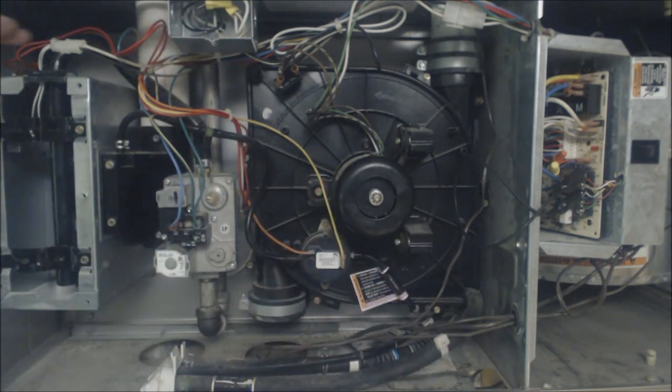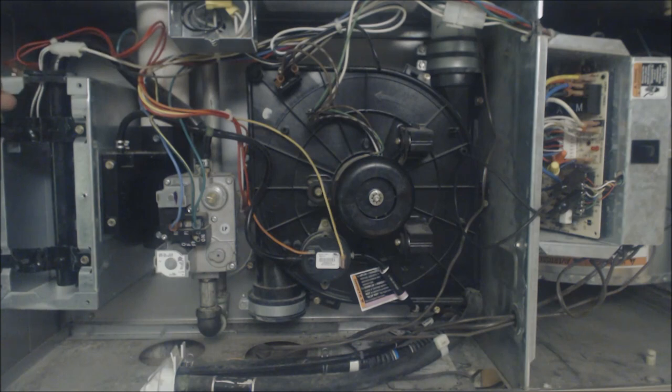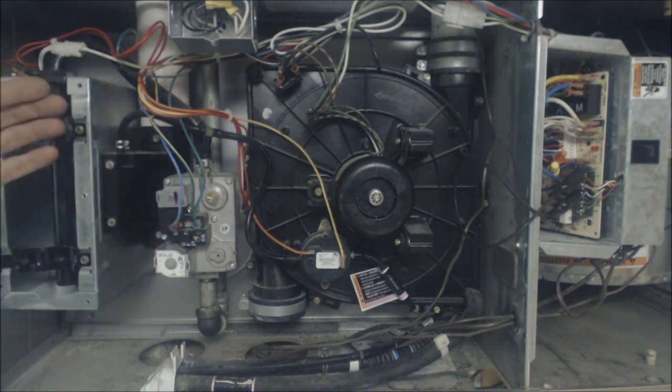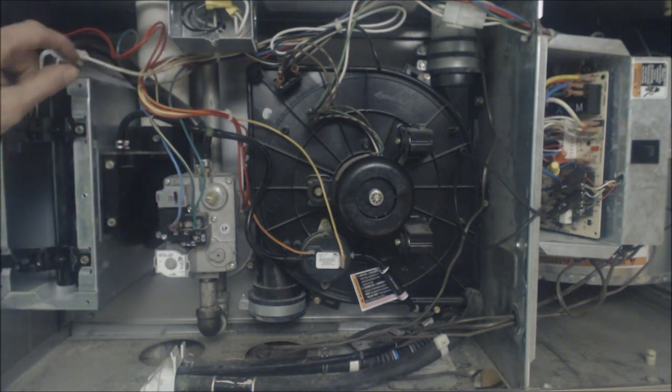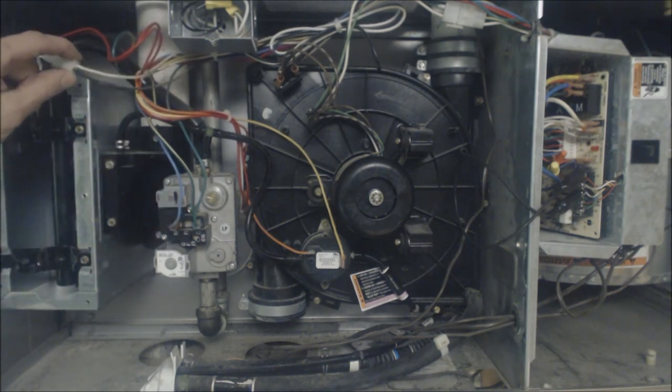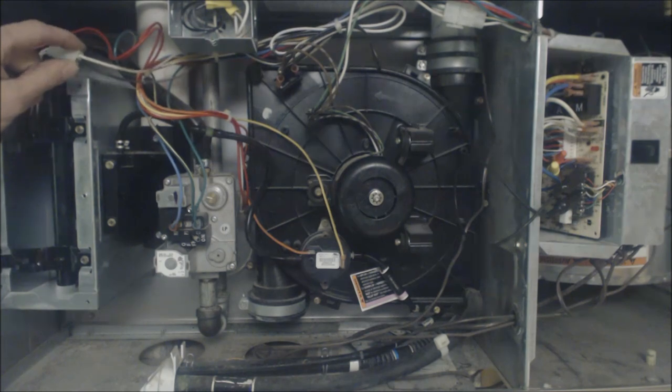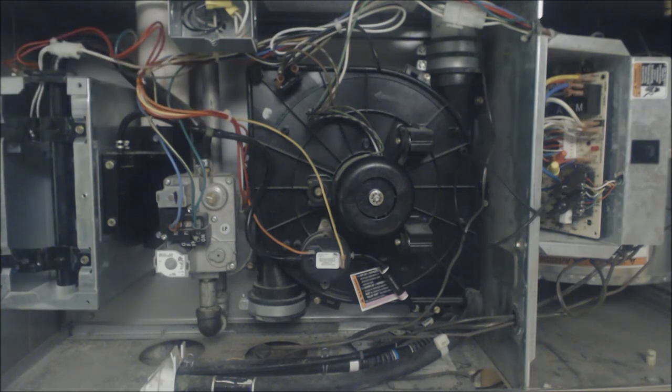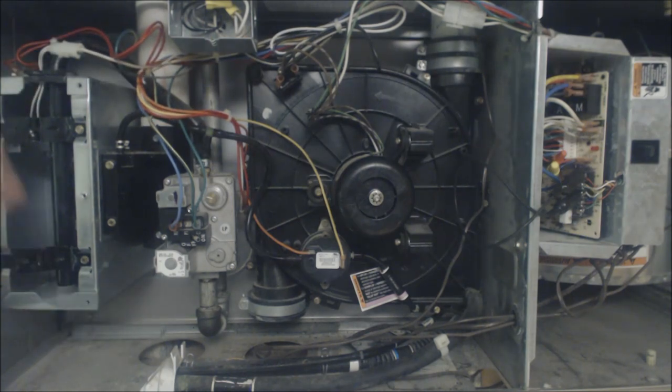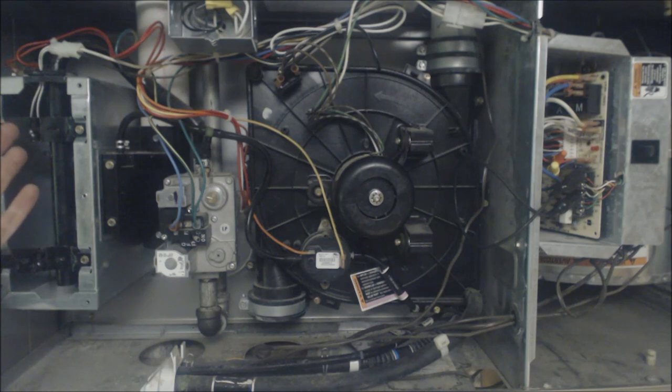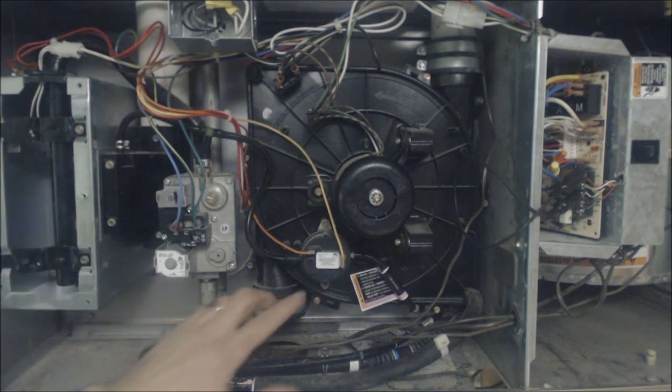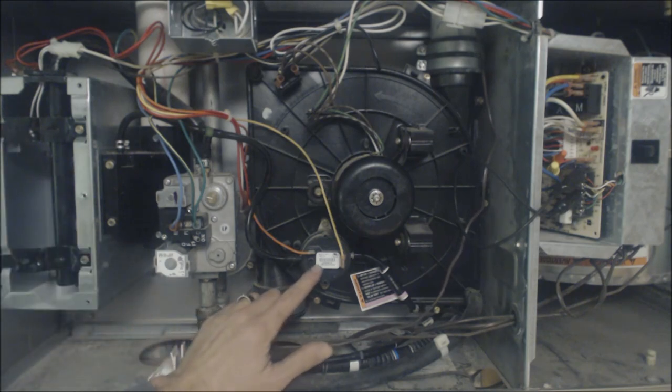So if something turns on, say inducer motor turns on, pressure switch closes, but the hot surface igniter does not turn cherry red, then you know that there's a problem either with the voltage going to the hot surface igniter or the hot surface igniter is bad.